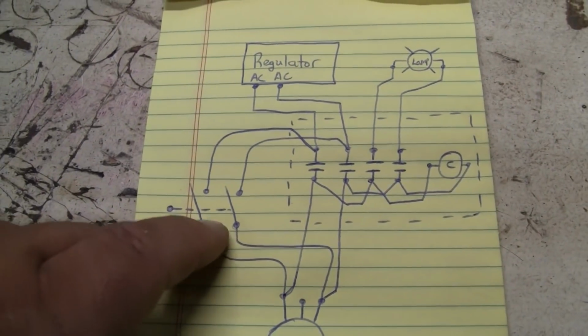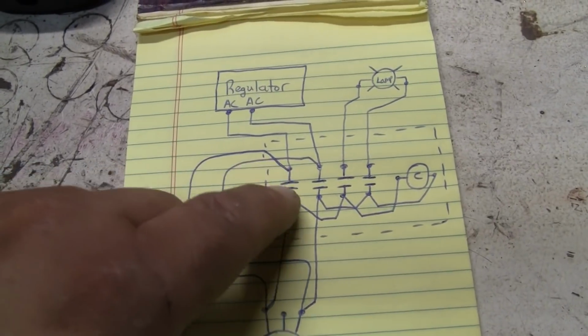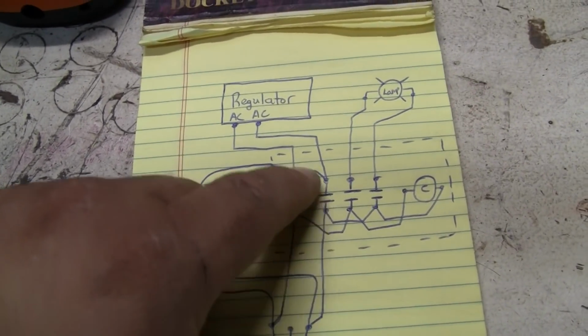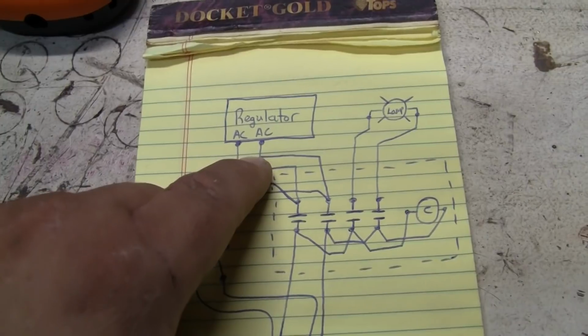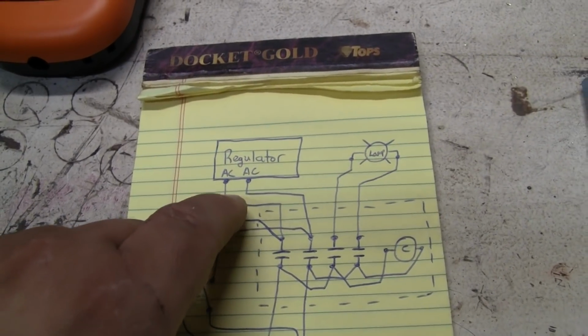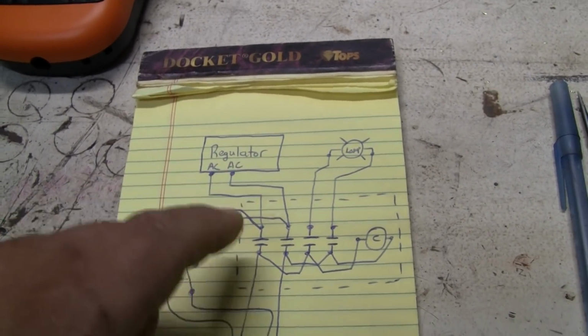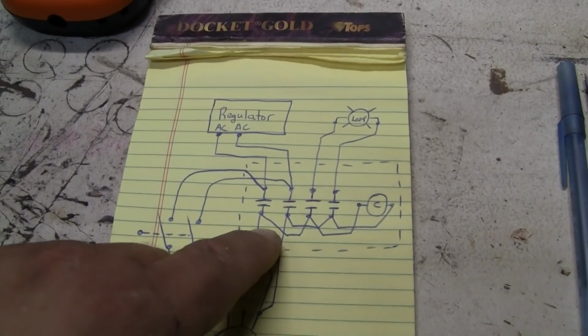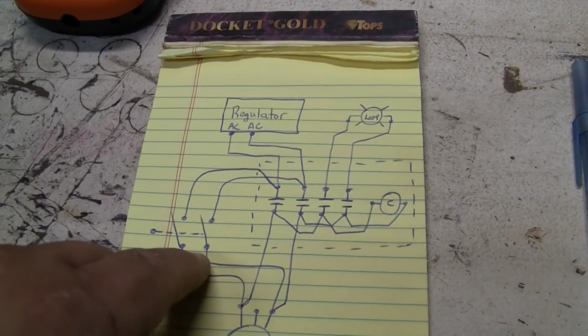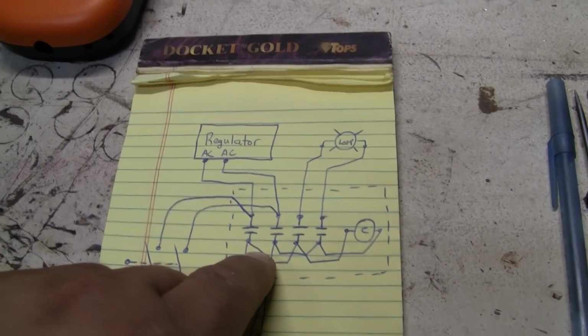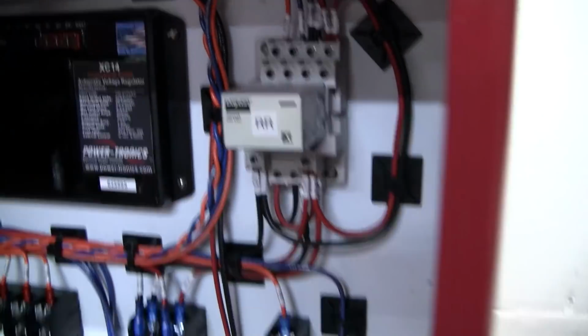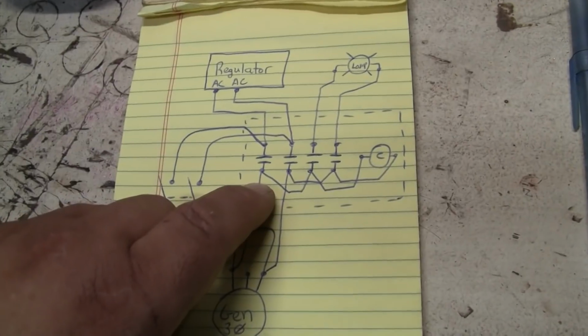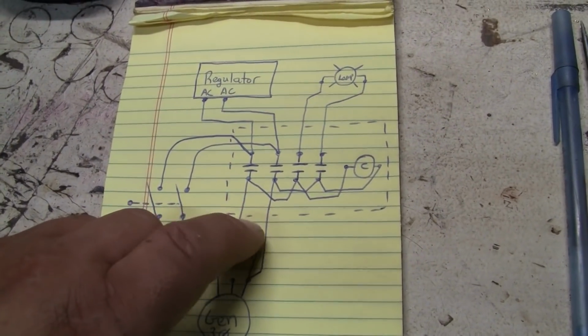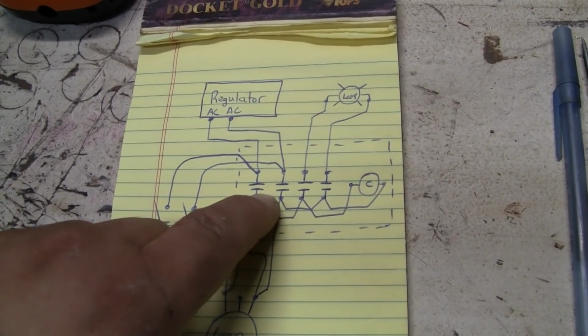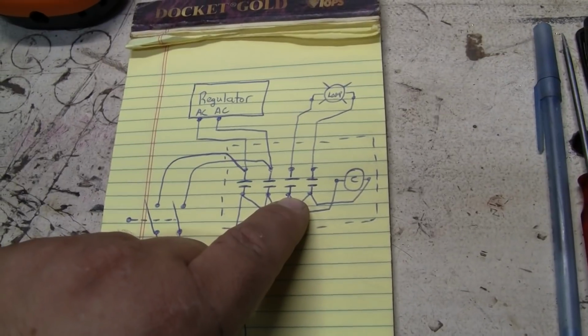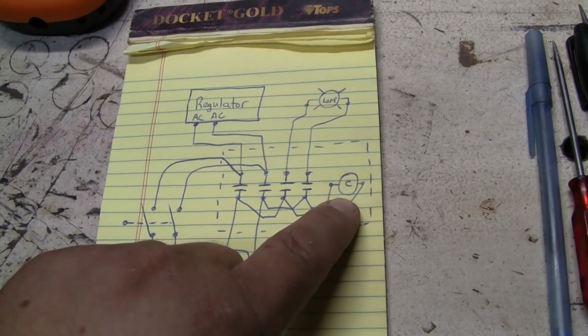When you close that toggle, power comes over around these relay contacts and directly feeds the voltage regulator. Once the regulator starts exciting the field and the gen output builds up, that also passes through the switch, but it also goes to the regulator relay right there. So it's a 4-pole relay. It comes out to 2 of the poles, jumps over to the other 2, and then jumps over to the coil of that relay.